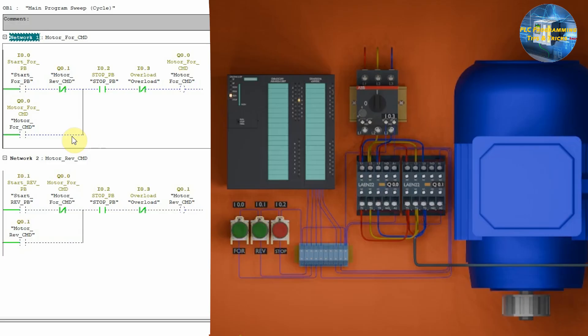Now, let's see the ladder logic for this application. In network one, we have written the logic to start the motor in the forward direction. We have inserted a normally open contact of push button I0.0 in series with the normally closed contact of Q0.1, which is the motor reverse command.